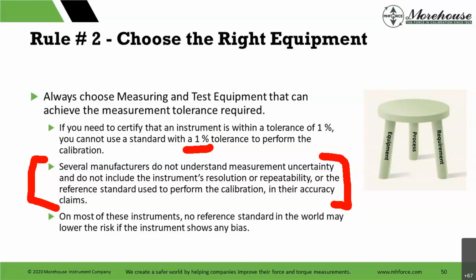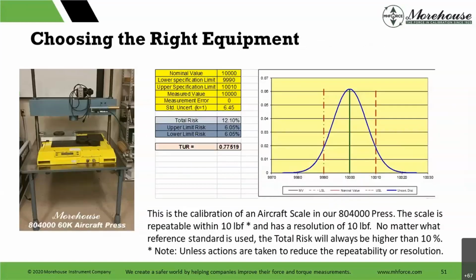Ask for test data. You're here. You can learn something. You can make your process a little bit different. And on most of these instruments, no reference standard in the world may lower risk if the instrument shows any bias. This is a situation of this. This is our old 8400 scale. This is an aircraft scale. It's a 60K aircraft scale. The instrument is repeatable within 10 pounds and has a resolution of 10 pounds, and the accuracy specification is 10 pounds. How is this possible?